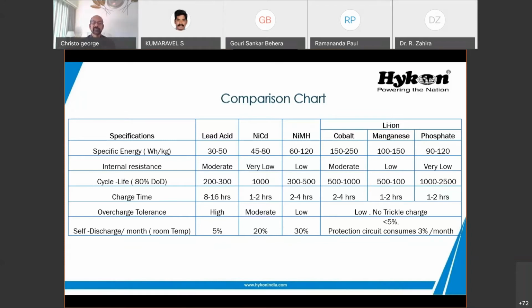Another is life cycle. If you look at lead acid, at 80% depth of discharge, you'll get 200 to 300 cycles. Nickel cadmium will get up to 1000. But if you look at LFP and others, other than manganese, it will get up to 1000 to 2500 cycles.